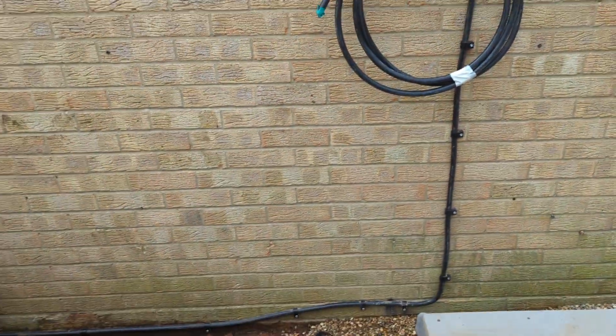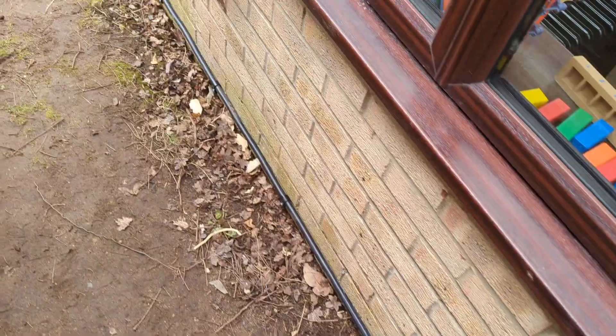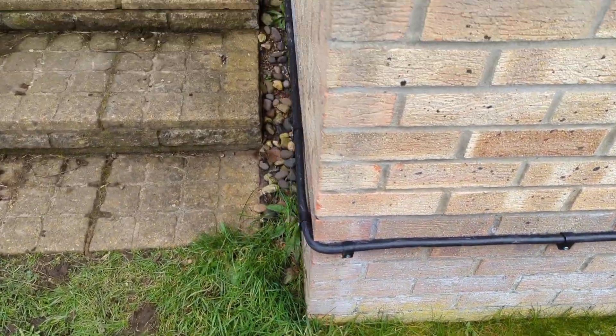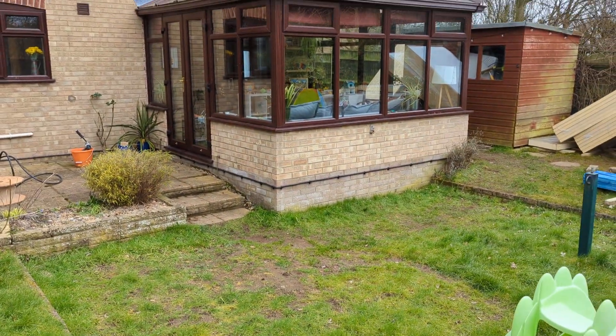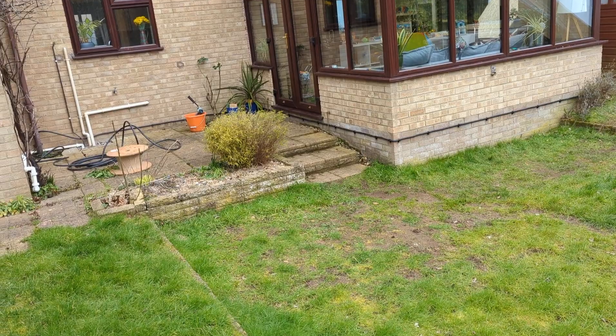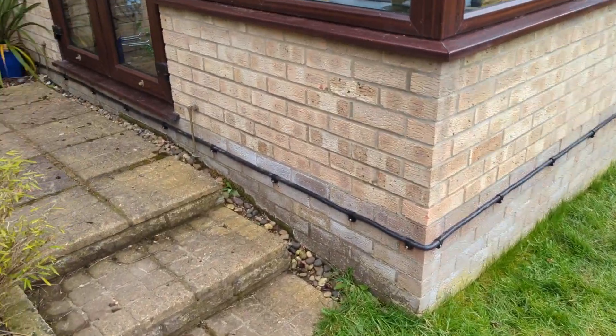I've just taped it off. There's 10 millimeter armored cable and it has been cleated to the wall. What I've been doing is drilling a 5 millimeter pilot hole and then using self-tapping concrete screws, impact driving them in with a Torx bit. Some might say it's not the prettiest thing in the world, but personally I kind of like it.